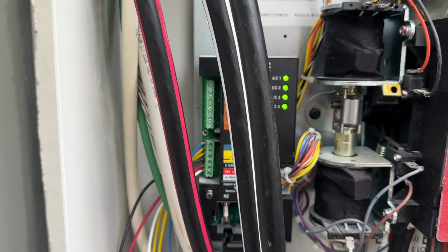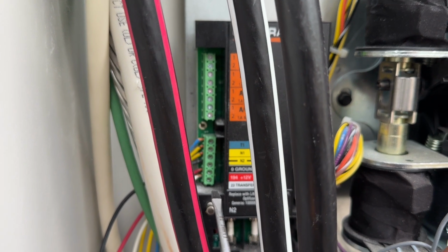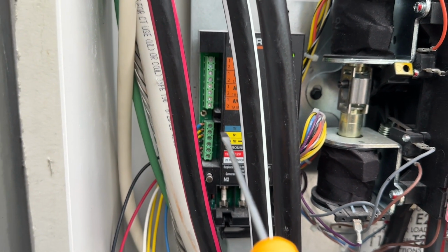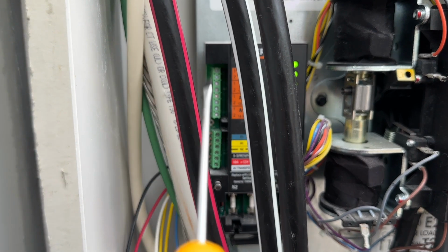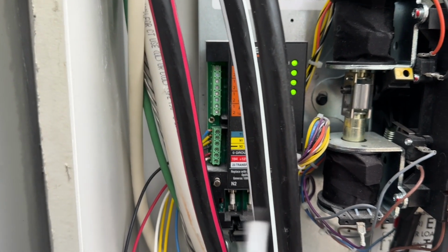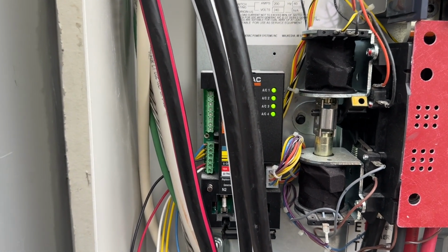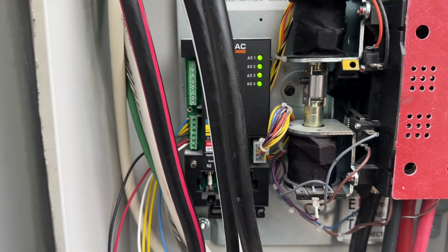Basically, error code 2099 indicates a voltage leak or a crossed wire scenario where maybe you crossed N1 and N2 over here, and then at the generator you have it the right way, or vice versa. In my case, I was going crazy. It says stopped alarm code wiring error 2099.